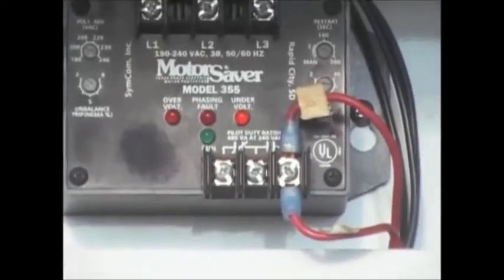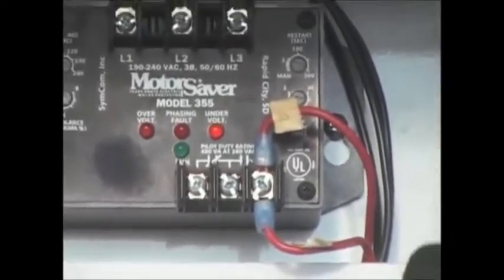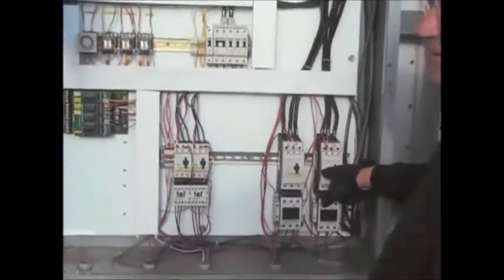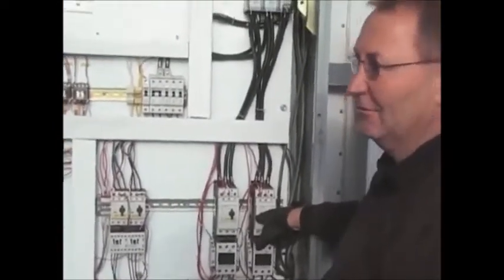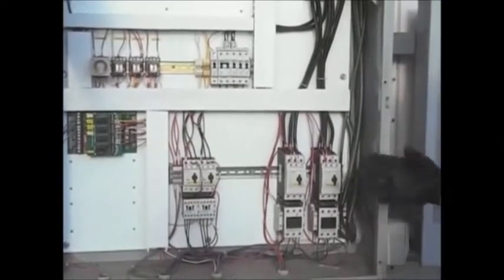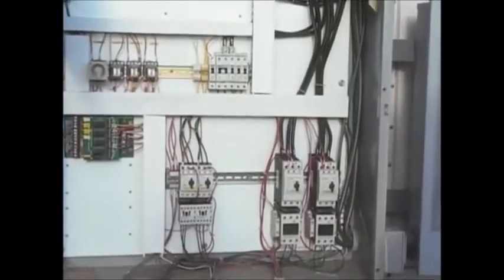It's a low-cost item, but even if this does not work, you do have overload protection on each individual motor, which would again trip out if you had high or low voltage or any kind of single phasing condition. Your motor starters would trip out. So that's the control panel in a nutshell. And then your main disconnect, which is fused inside, and that's the basics of the controls.